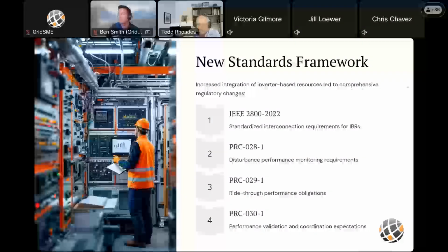One is a non-NERC item, IEEE 2800, which is really a foundation of a lot of the work that NERC has been doing and the direction being taken. Then there are 3 NERC standards, PRC 28, PRC 29, and PRC 30, which directly relate to the ride-through performance or operational performance of an IBR plant, as well as validation and coordination aspects of the plant, and data collection and monitoring of performance. We'll go into details of each of those.